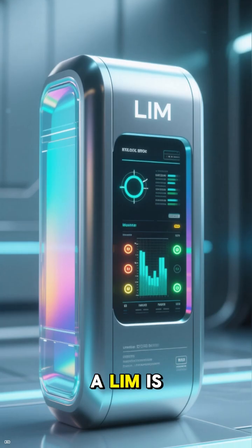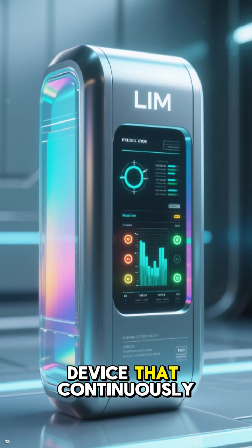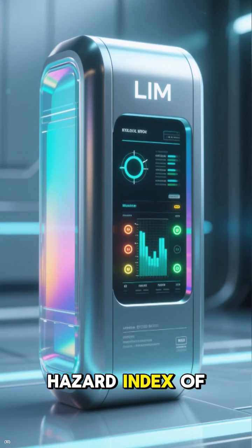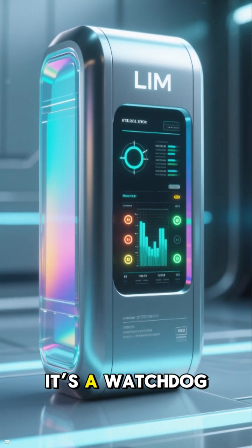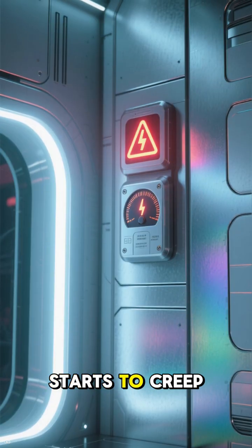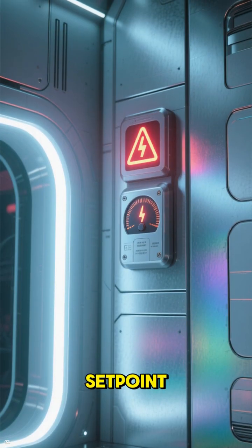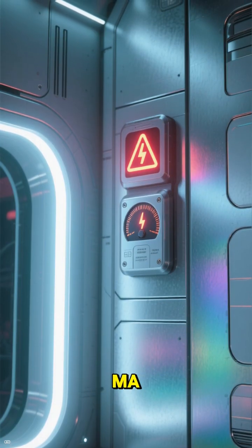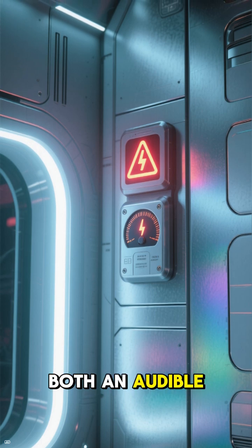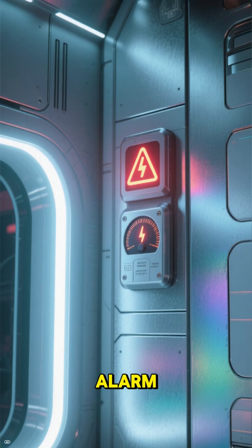A LIM is a fantastic device that continuously monitors the total hazard index of the system in real time. It's a watchdog. If the total hazard current starts to creep up and approaches the alarm set point, which is typically set at 5 milliamperes, it will trigger both an audible and a visual alarm. This immediate feedback is invaluable.